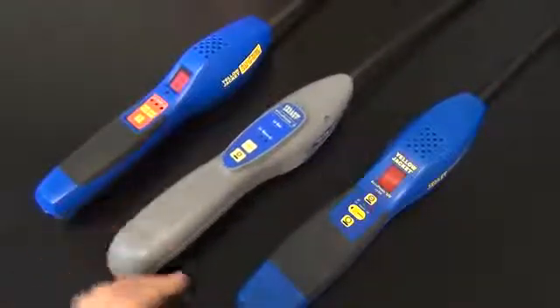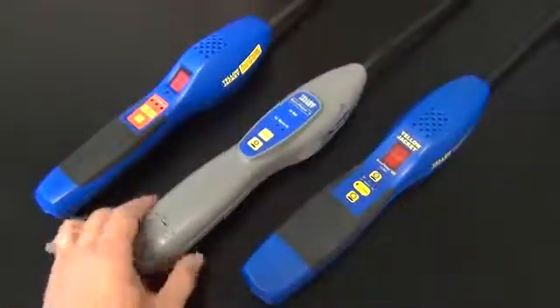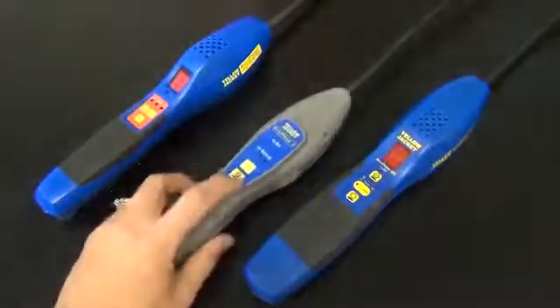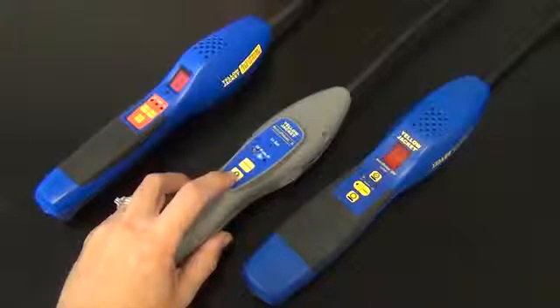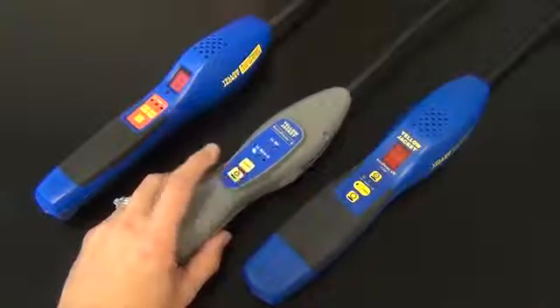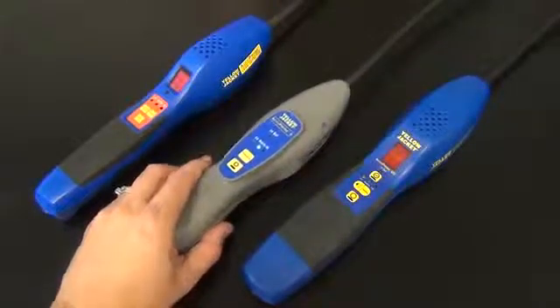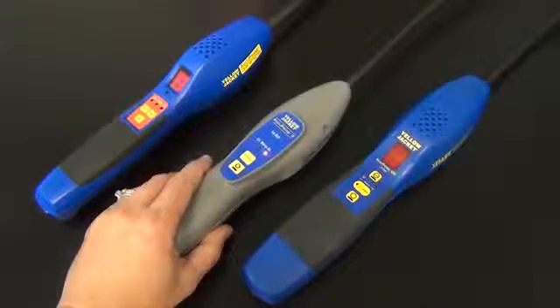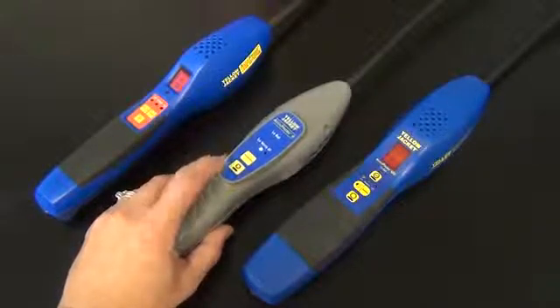On the AccuProbe 2 and the AccuProbe UV, the unit will still turn on, but what will happen is it won't come out of the warm-up mode. It will just continue to cycle and cycle, but will never come out of the warm-up mode.